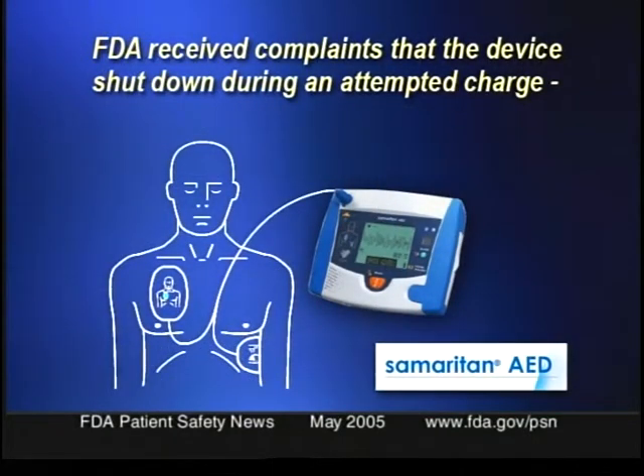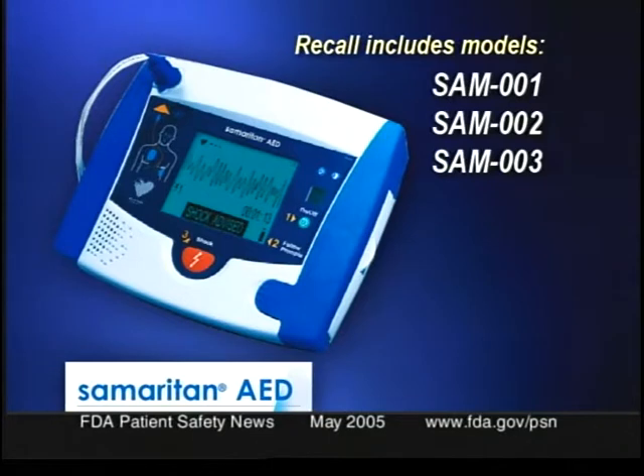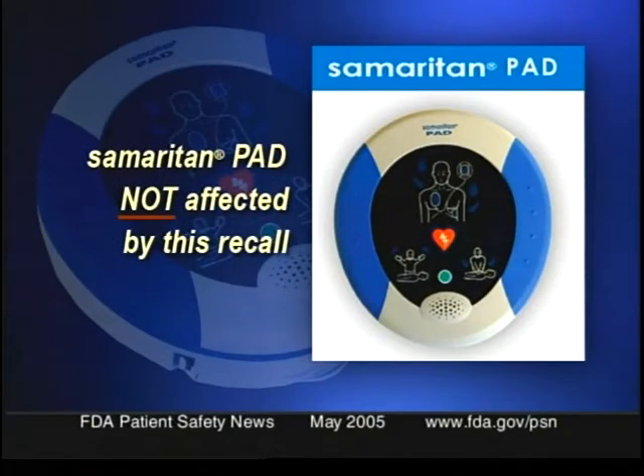HeartSine Technologies is recalling some of its Samaritan automatic external defibrillators. The affected devices may shut down before delivering a shock, which could delay treatment or even lead to death of a viable patient. Several user complaints have been received that the device shut down during an attempted charge, but no injuries have been reported to date. This recall includes models SAM001, 002, and 003, with certain serial numbers within the range of 1270 to 2324. The HeartSign Samaritan PAD automatic external defibrillator is not affected. HeartSine Technologies notified its distributors and customers by letter on February 14, 2005, and the company is providing a software upgrade for the affected devices. If you have a device within this serial number range but have not yet received an upgrade kit, contact the company as soon as possible. Go to our website for details on how to contact the company.